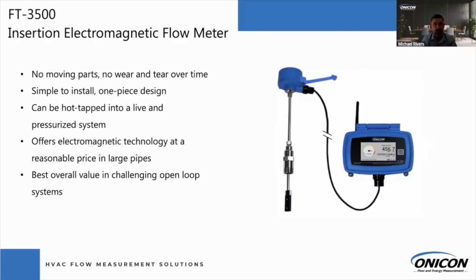So no moving parts means less wear and tear over time. It's also a one-piece design. You can hot tap it into a live and pressurized system, which means it's really good for new construction, but also retrofit applications. Also, with insertion style meters, it doesn't matter what the pipe size is. Whether it's a 2-inch pipe or a 36-inch pipe, you're getting that mag meter technology at the right price. So overall, this is really the best solution for open loop systems.